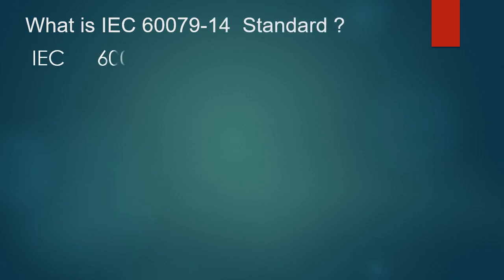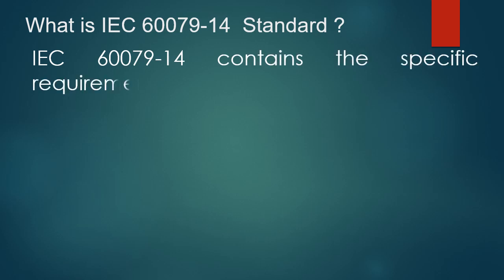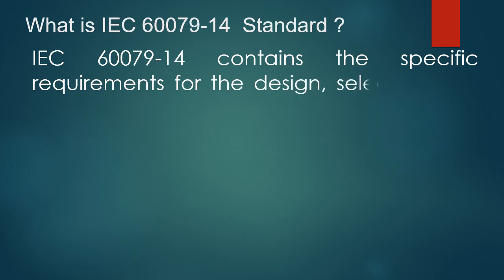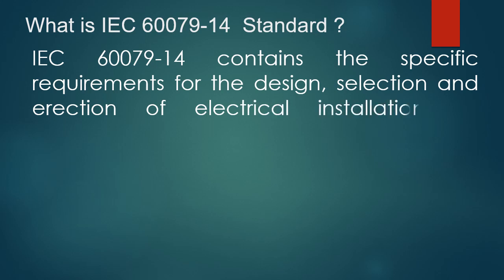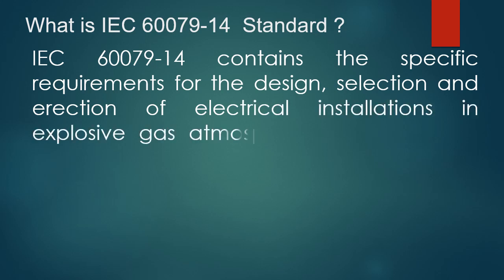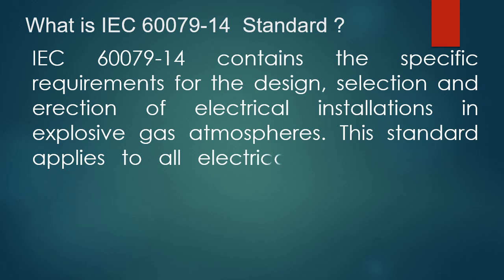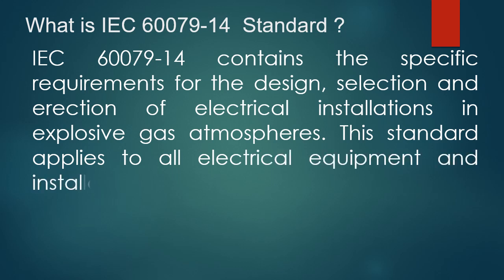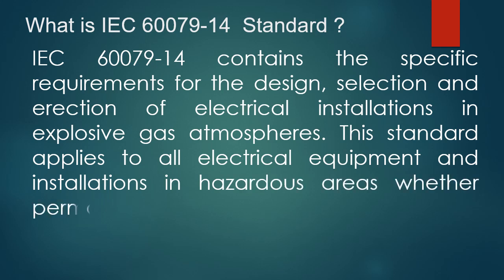What is IEC 60079-14 standard? IEC 60079-14 contains the specific requirements for the design, selection, and erection of electrical installations in explosive gas atmospheres. This standard applies to all electrical equipment and installations in hazardous areas, whether permanent, temporary, portable, transportable, or handheld.